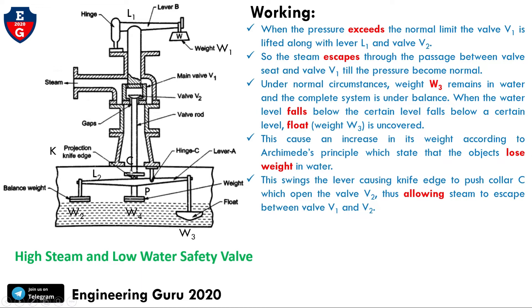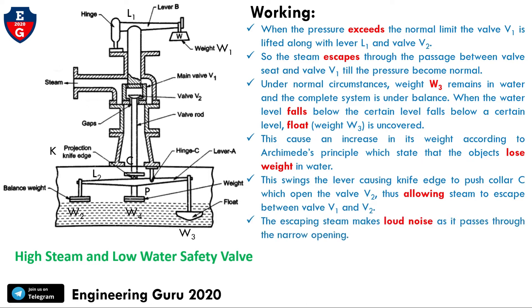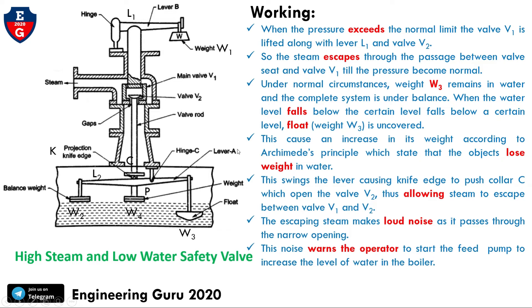The swing of the lever causes the knife edge to push the collar, which opens valve V2. This hemispherical valve opens, allowing steam to escape between valves V1 and V2. The escaping steam makes a loud noise as it passes through the narrow opening, warning the operator to start the feed pump to increase the water level in the boiler.